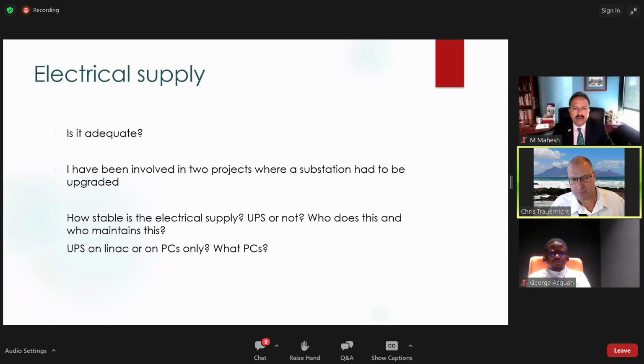LINACs don't use a ton of power, but you should at least be aware of it. And in some projects, if your building's sort of on the limit, you're going to have to upgrade the substation. Think about it. You may or may not have to specify it. In South Africa, we have fairly unstable electricity supply. So all our new LINACs come with uninterrupted power supplies, massive battery banks that need an extra room to go into.